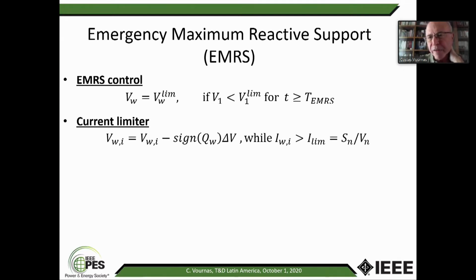There may be cases where the limit is a little bit above the nominal, but let's take this as a limit right now. So what happens if you are above the limit? Then if you are giving reactive power, you lower your voltage, okay? Because you are below the limit, but you also want to lower the current. So this algorithm is such that when you are supporting with reactive power and you have reached the limit, you have to lower the voltage in order to lower your current.